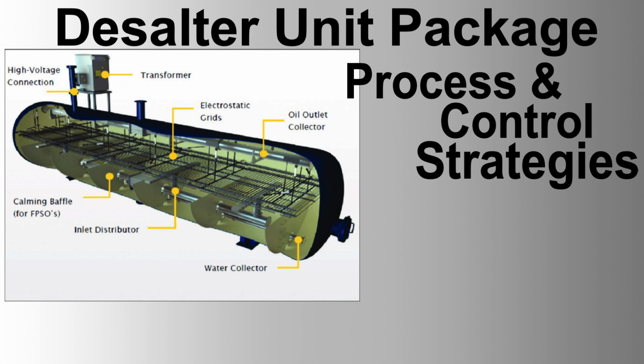2. Water injection system. Start the water injection system and adjust the flow to achieve the desired crude oil to water ratio. 3. Crude oil inlet. Gradually open the crude oil inlet valve PV301 to start feeding crude oil into the desalter. 4. Mixing. Ensure that the crude oil and water are thoroughly mixed in the mixing valve or static mixer.